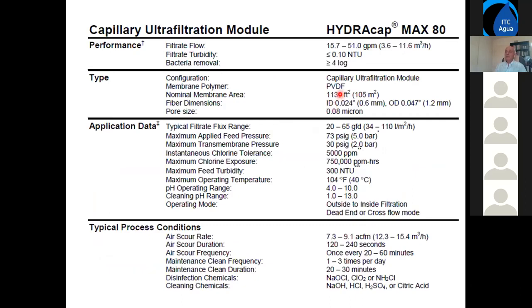Okay, so it's made of PVDF. The advantage of this membrane is that they do not use water for backwash. Actually, do not use water backwash, use only air scouring. Using some water for flushing, but otherwise they're only using air scouring. Their recovery rate, utilization of the feed water is very high, could be as high as 96%. Other membrane usually have 90 to 92%. So this is big advantage in the system where there's limitation on disposal of the wastewater.